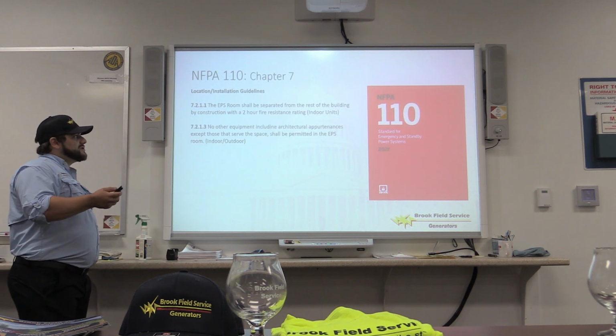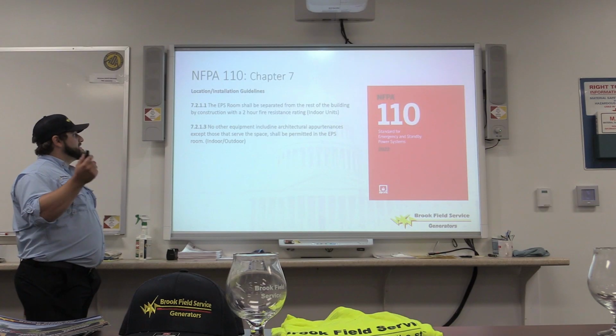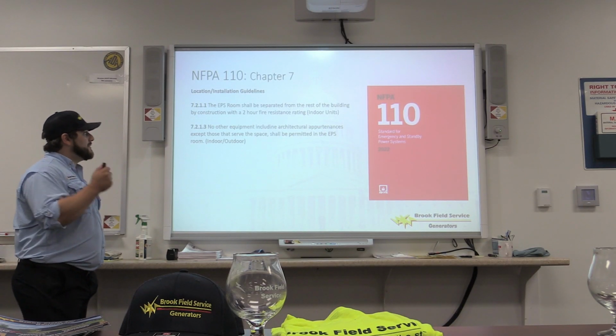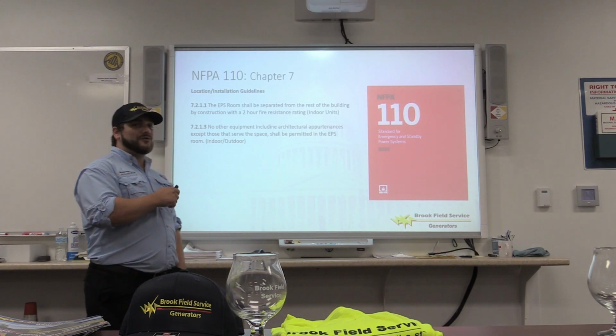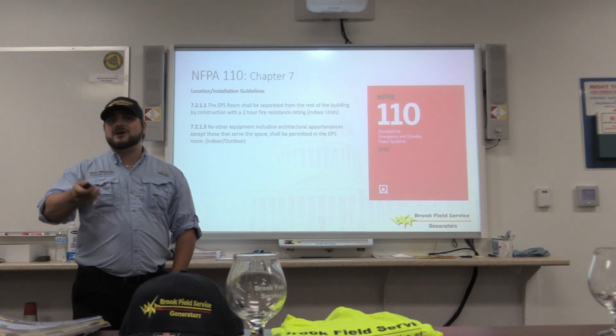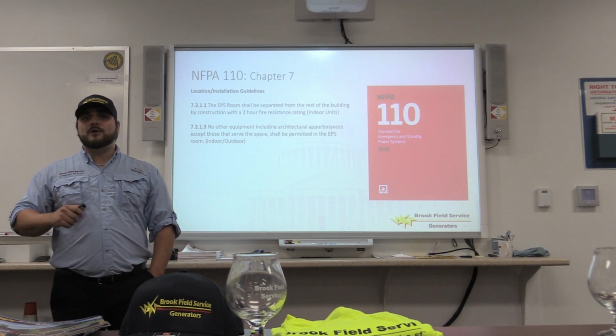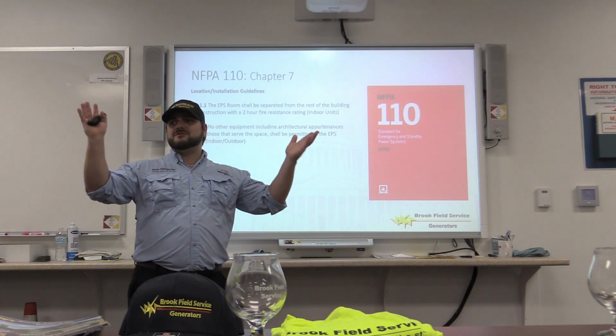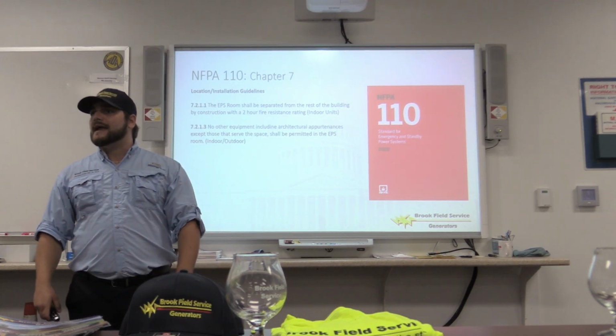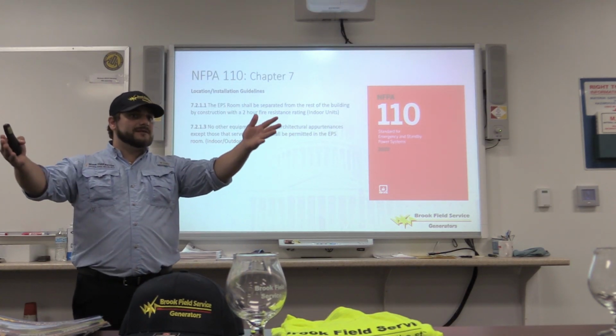No other equipment, including architectural appurtenances except those that serve the space, shall be permitted in the EPS room, both indoor and outdoor. We've seen too many times, Josh, where you have boxes and ladders blocking the ATS or the system itself.